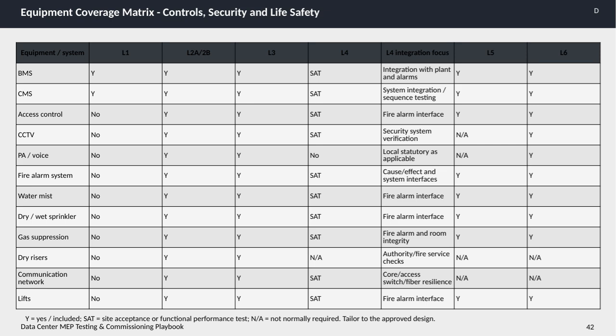The notation Y indicates inclusion at each test level. SAT identifies where site acceptance or functional performance tests occur, and not applicable signals when testing is not normally required. Overall, this matrix helps guide the structured testing and commissioning process, ensuring every critical system is validated appropriately and integrated seamlessly for operational readiness and safety compliance.